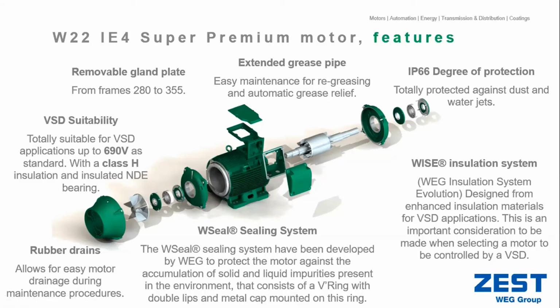There are drain holes for de-humidization. Any humidity that builds up in the motor has a way to escape, through a special WSeal sealing arrangement. This also helps us obtain an IP66 degree of protection, meaning the motor is totally protected against a water jet.